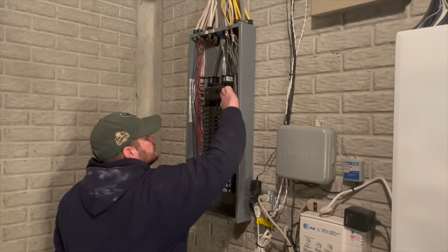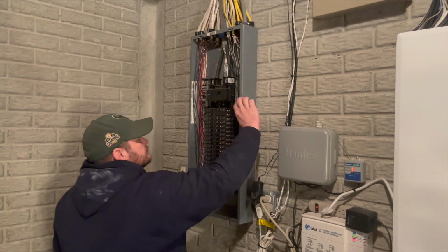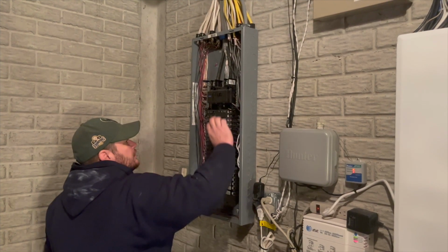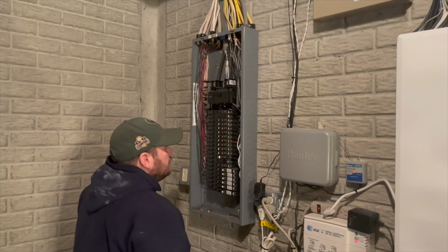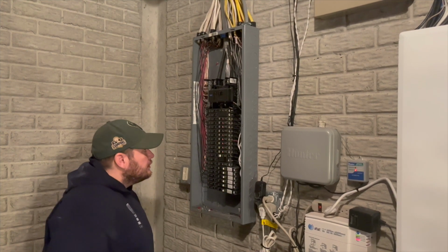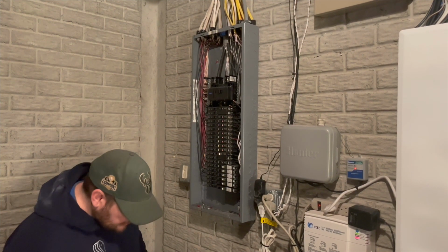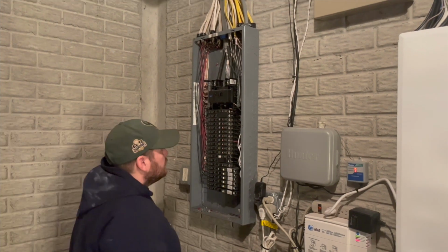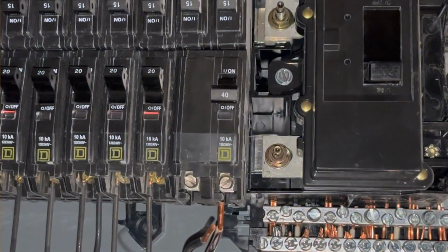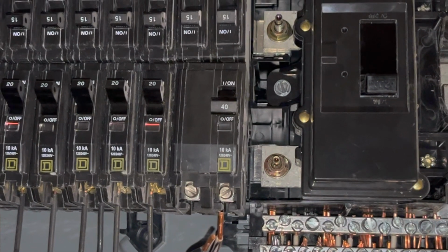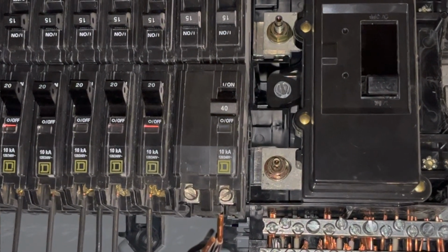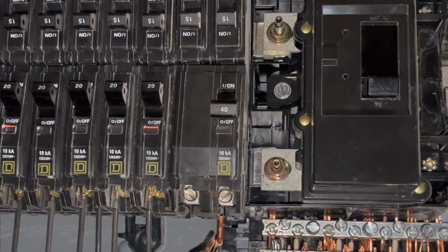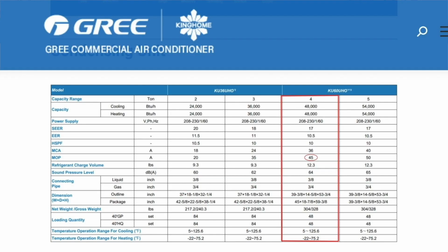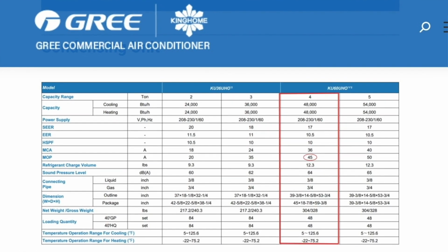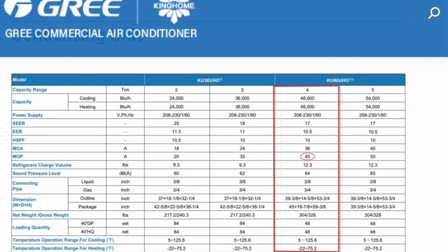Now, before any mechanical work gets started, we have to make sure that the electric service to the heat pump is sufficient. The heat pump in operation will use less power, but sometimes the same size heat pump will require a larger electrical service. This is such a case. So you can see here that I have a 40 amp circuit breaker, which matches the power requirement for the existing Carrier air conditioner.